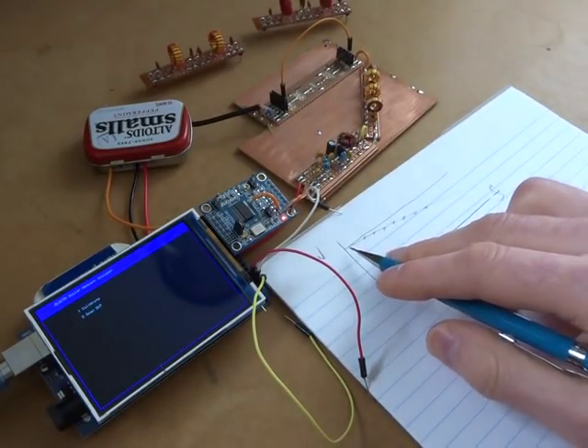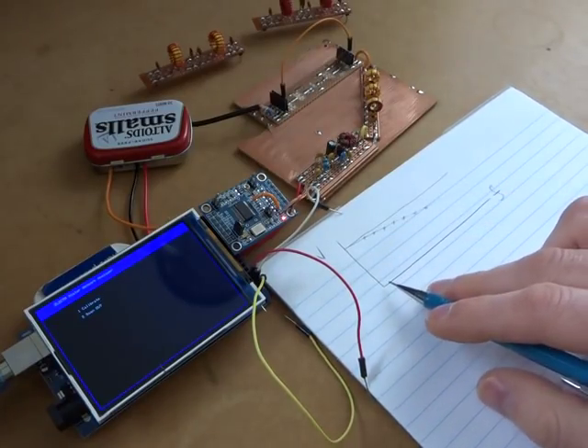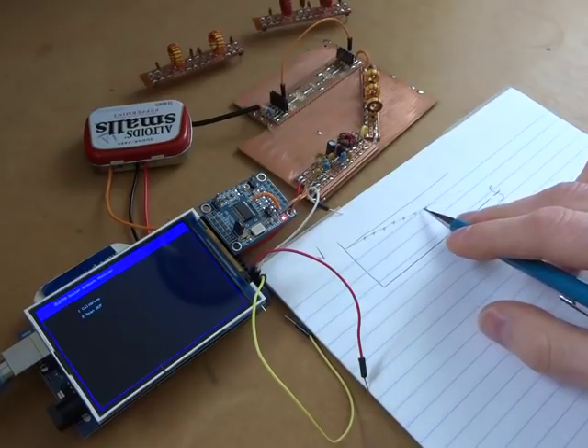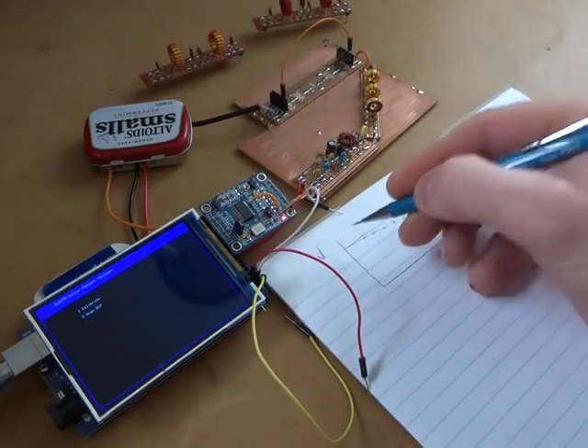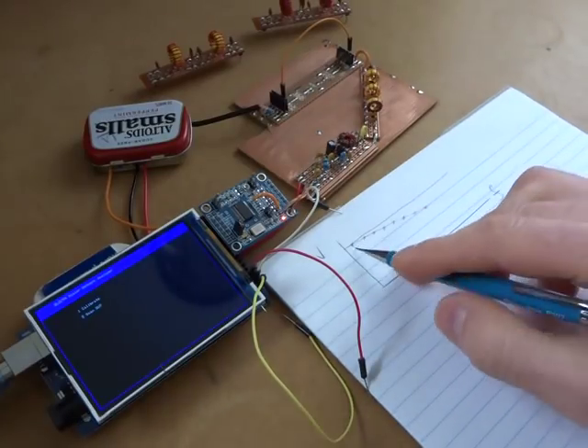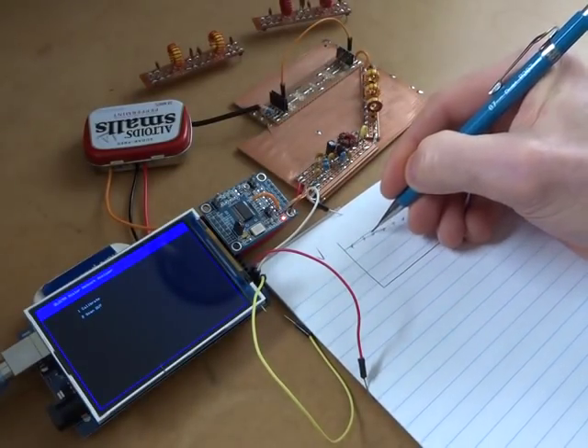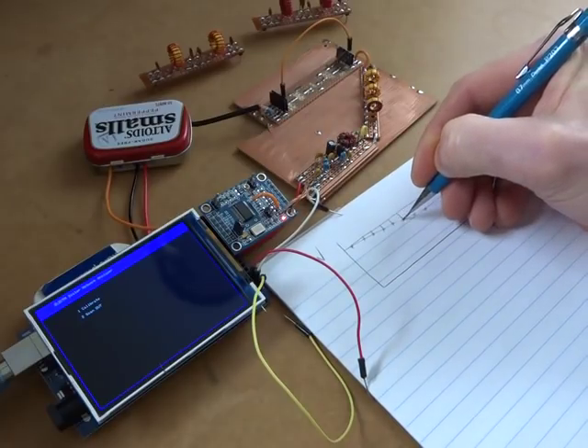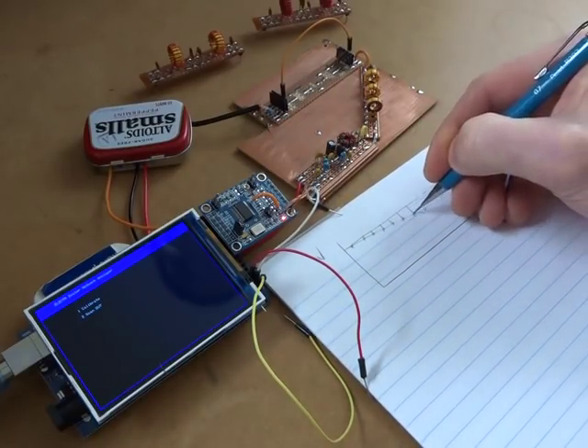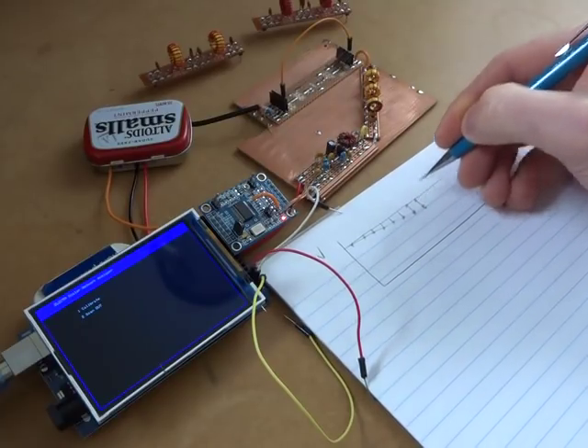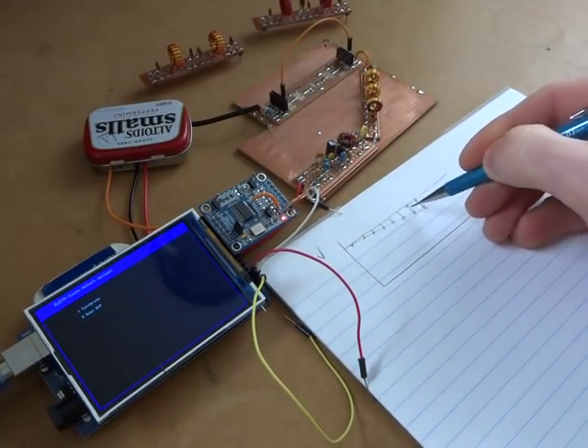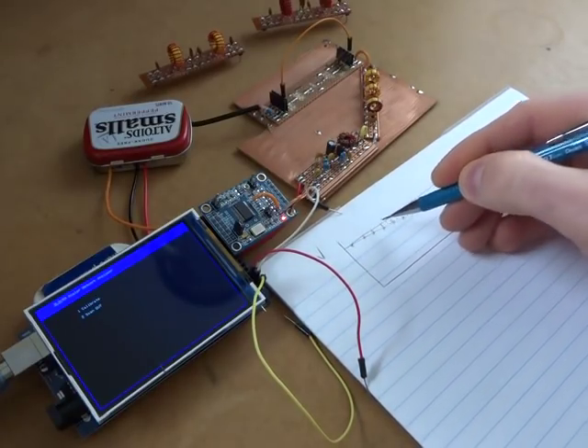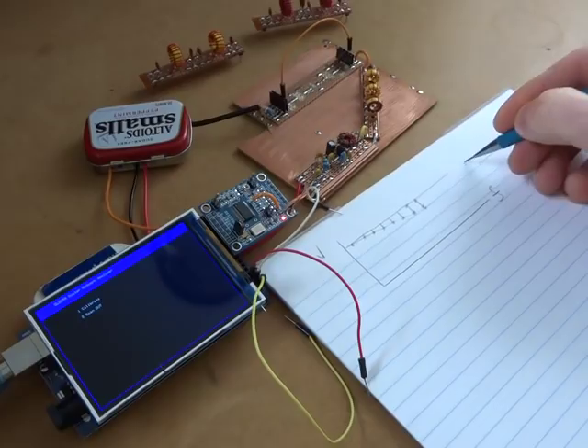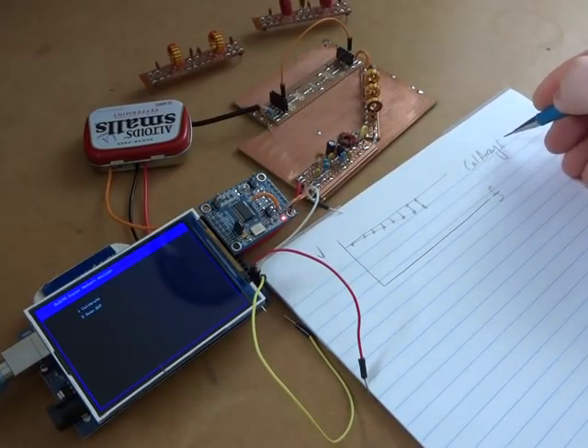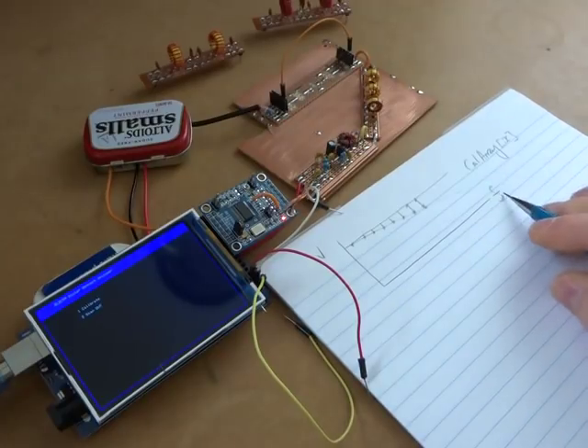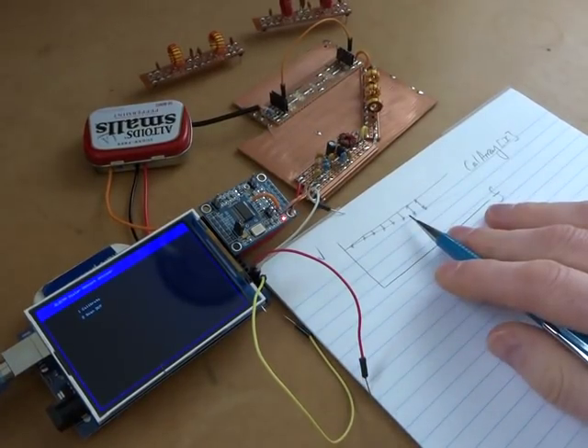At the conclusion of running through the calibration, in other words, determining what those various points are across the range, it then doubles back, finds out what the maximum reading was, and then runs back through the array to determine what the error voltage is between the ideal maximum constant voltage and the individual test voltages via frequency. Those error voltages, or offsets, whatever you want to call them, are then stored in our cal array for the various frequency points. So that's the calibration array.